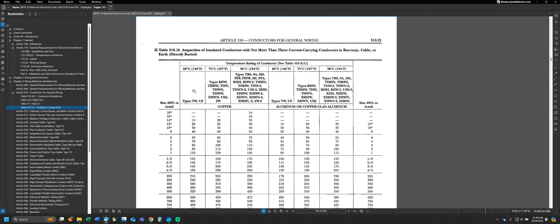In the 60°C column we have types like TW, UF; in the 75°C column we have types RHW, THHW, and so forth; and in the 90°C column we have common conductors like THHN, THHW, XHHW, XHHW-2, and so forth. What the NEC is telling us is that these insulation ratings can essentially be heated up to their rated temperature without negatively affecting the rating or condition of the insulation.